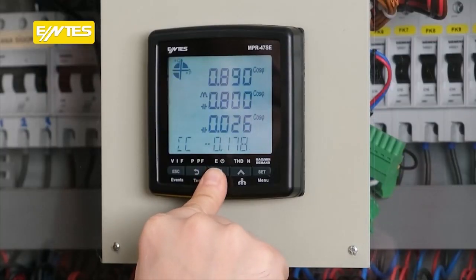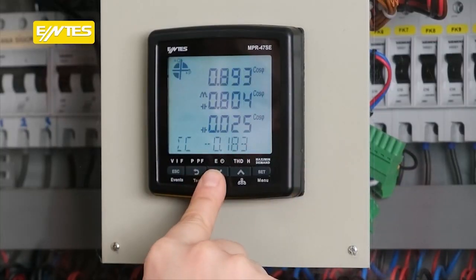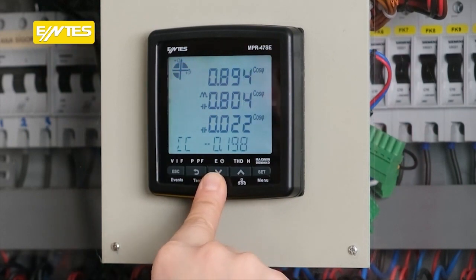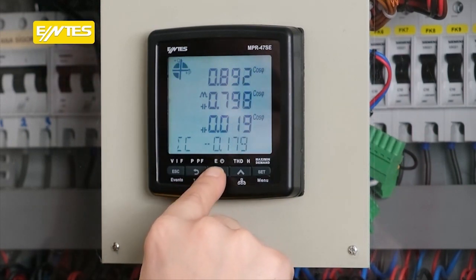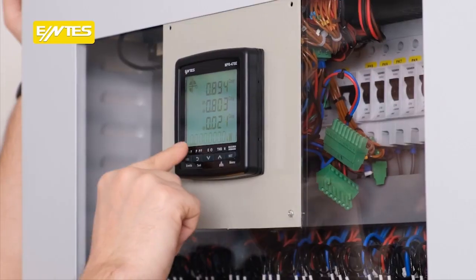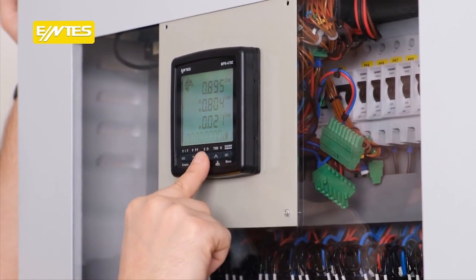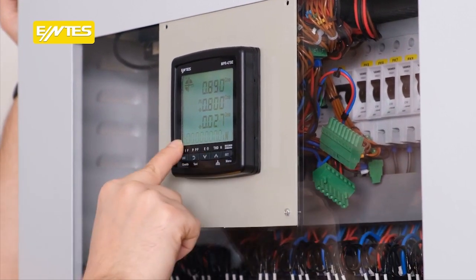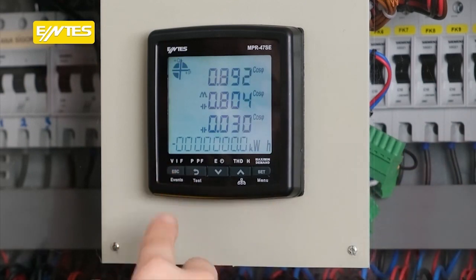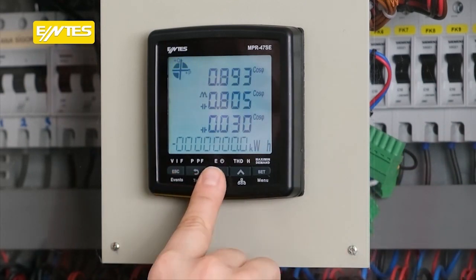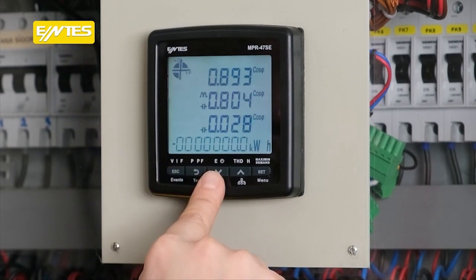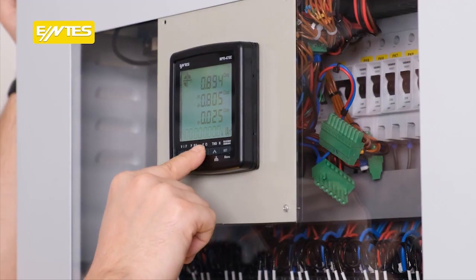Since there is an energy meter menu on the device, we can measure the electricity we produce and consume in the grid. Since it measures reactives here, it is with actives. When we press the E key, we're greeted with a kWh screen. There is a measurement of the energy parameter at this location. When we generate and supply energy to the grid during periods of surplus, as is found in solar power plants and wind power plants, there are also bidirectional counters for the same parameters.